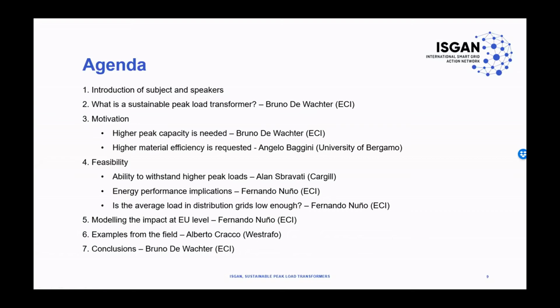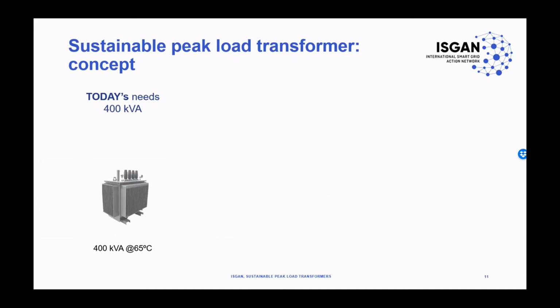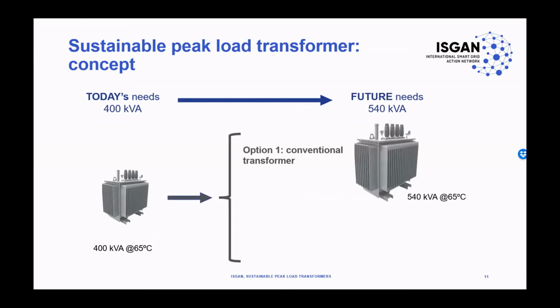Yeah, so this is the agenda of today. We will go into detail later, but I would like to start with a short introduction to the concept of the sustainable peak load transformer. So suppose you have a 400 kVA distribution grid transformer. This 400 kVA maximum peak load limit is there because the maximum temperature rise in the windings is 65 degrees Celsius. This is a limit for the insulation, and this figure has been there already for a very long time. Now suppose that you expect an increase in the peak load of your distribution line, and you want to upgrade this transformer, let's say to 540 kVA. Then there are two options.